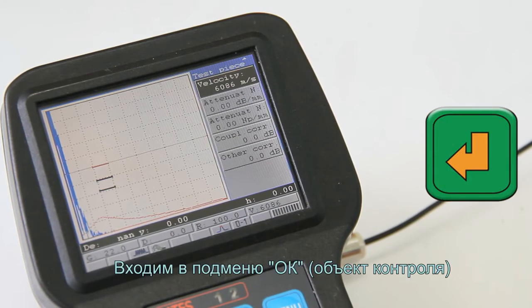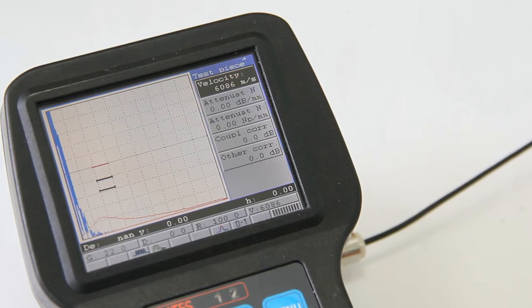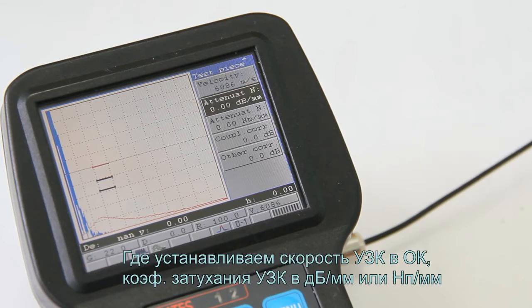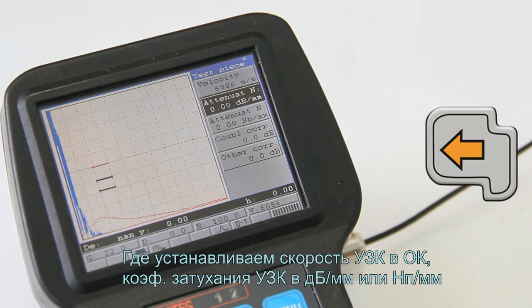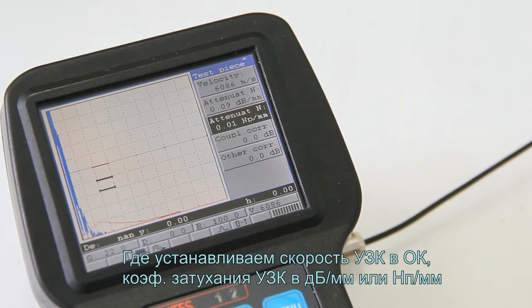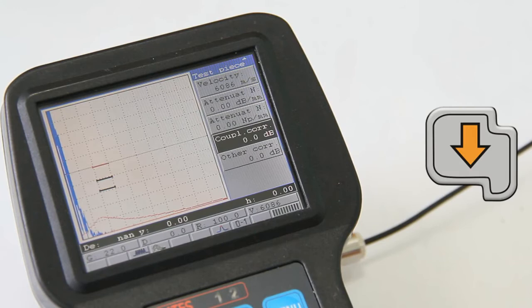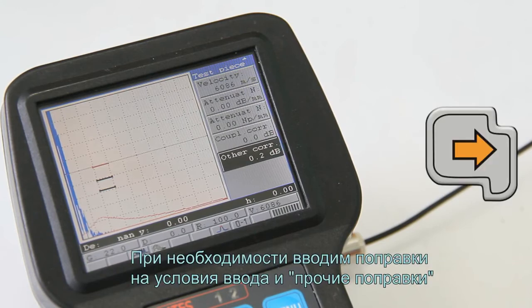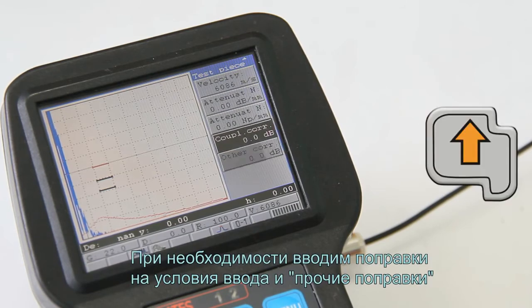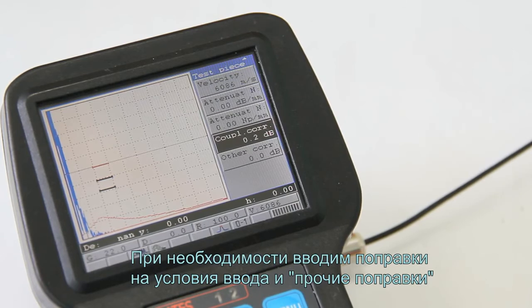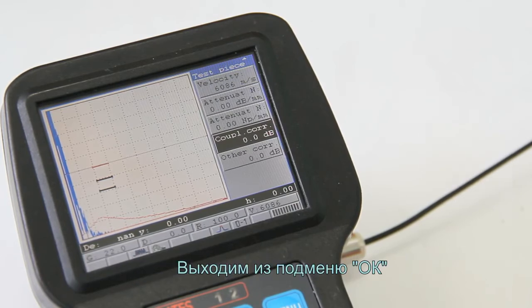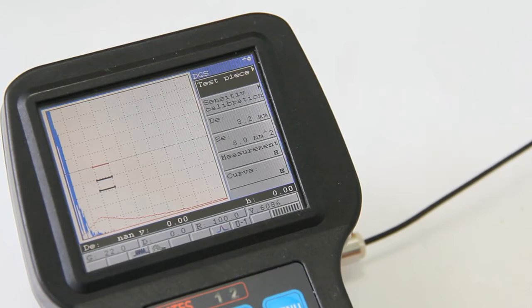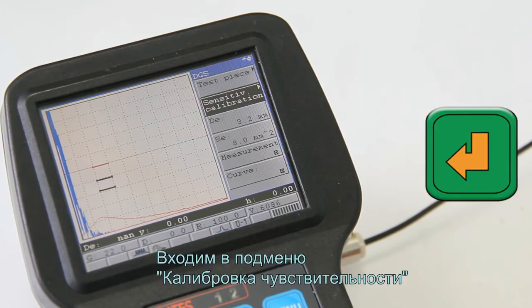Enter the Test piece submenu, where set up the velocity, attenuation N and dB per millimeter or Np per millimeter. If required, enter coupling corrections or other corrections items. Exit the Test piece submenu. Enter the sensitivity calibration.